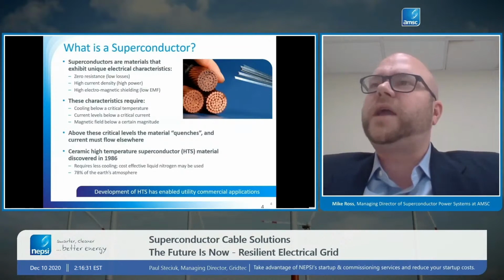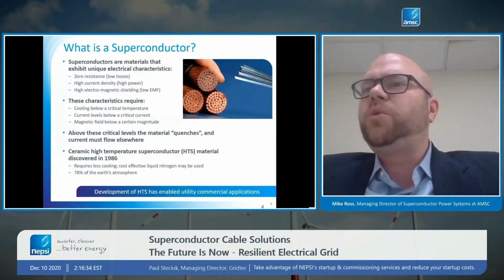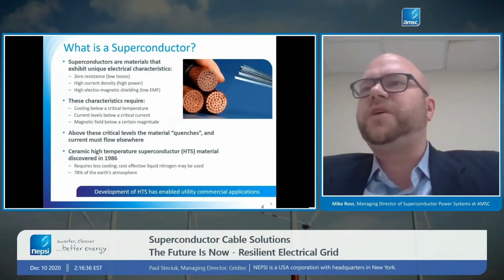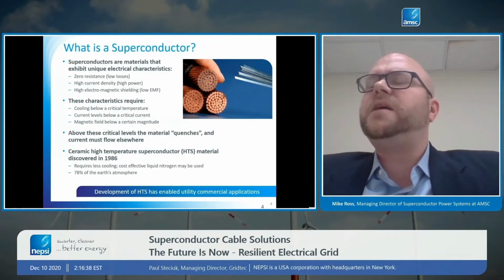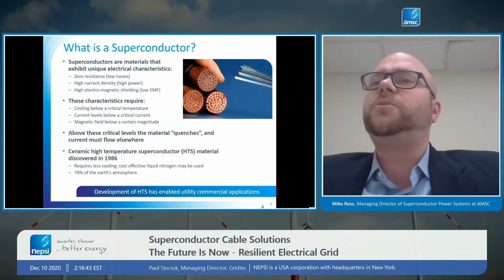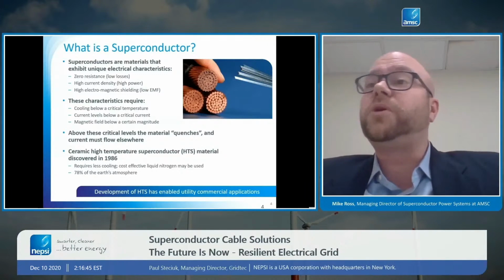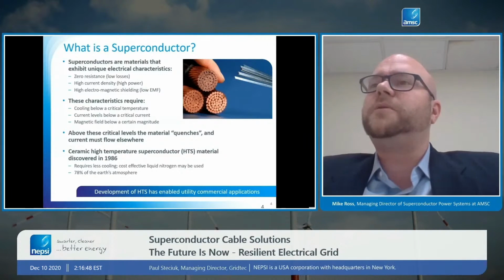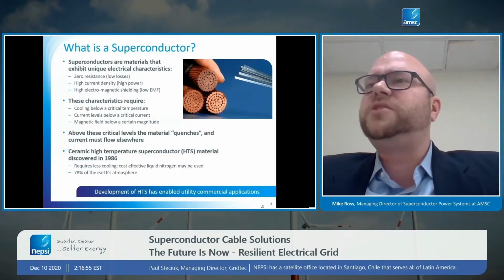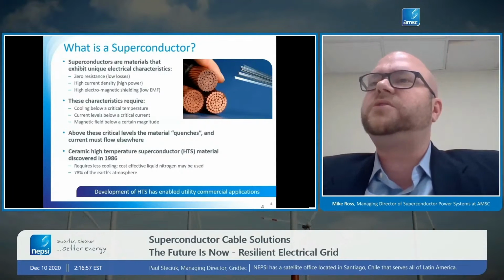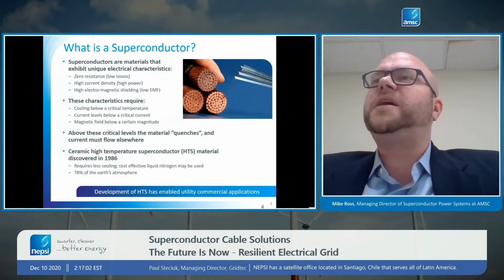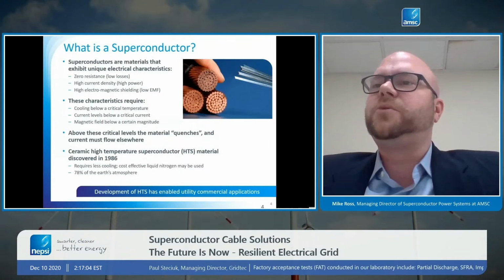So when we're making a power cable out of these wires, and we rate that power cable for 3,000 or 4,000 amps or whatever it might be, and then we use that power cable in a system, and then there's a fault on the system somewhere, so we try to drive 30,000 or 40,000 amps through that cable, it stops being superconducting. What that means is it becomes resistive, and that transition from being superconducting, non-resistive, to being resistive adds impedance to the system that limits the amount of fault current through the cable.